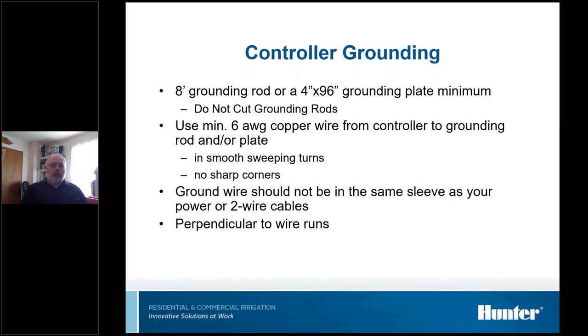And then Dave, I got something to add too on that grounding. I get this question a lot: what's the recommended depth to bury a ground plate? I see the recommendations at either 30 or 36 inches, and any place down in that area is good. Once you get down to about 3 foot deep, there's almost always moisture far down in the soil, and it's that moisture that we're looking for. It helps conduct electricity.